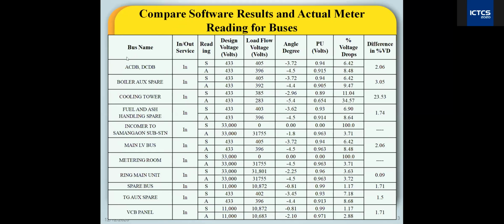I have noted the bus names: ACDB, DCDB, boiler house, and cooling tower. I have mentioned the different locations of my plant, and found that for the ACDB and DCDB bus, there is only 2.06% voltage drop occurring. The software detected 6.42% at that point, but actually it takes place at 8.48%. So here we have taken 5% as our reference, but we got 8.48%, meaning we have to take action and reduce that voltage drop below 5%.